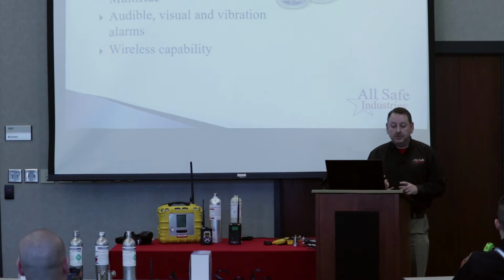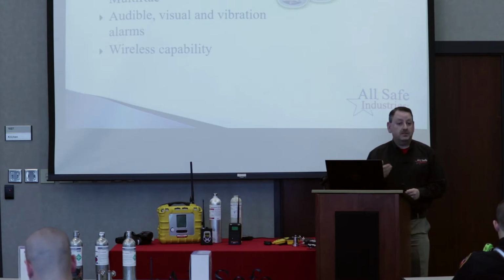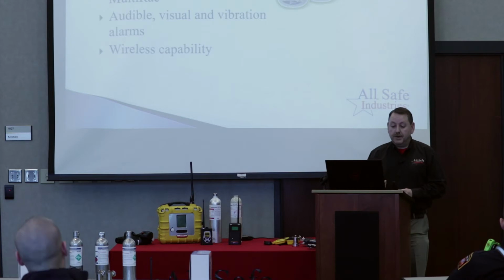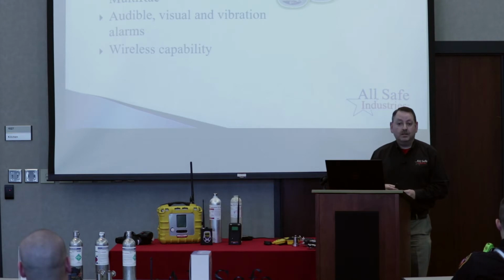We can do AutoRae Pros for LEL, for infrared sensor, for a PID, so you can actually get a PID that small if you just want a PID only, and of course toxic gas. The cool thing is it uses the same exact sensors as your MultiRAE. So you would be able to interchange those sensors between any of the instruments, and it's going to be helpful on your part down the line because we're using the same parts in the single gas ToxiRAE Pro as we're using in your MultiRAEs. You're going to get an audible, a visual, and a vibration alarm, and this instrument is wireless capable, and you guys did purchase it with the wireless capability, so we'll be talking more about that as well.